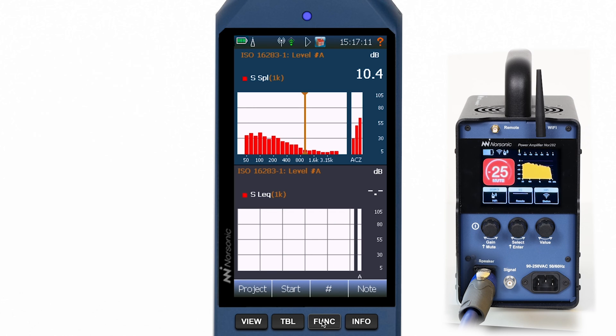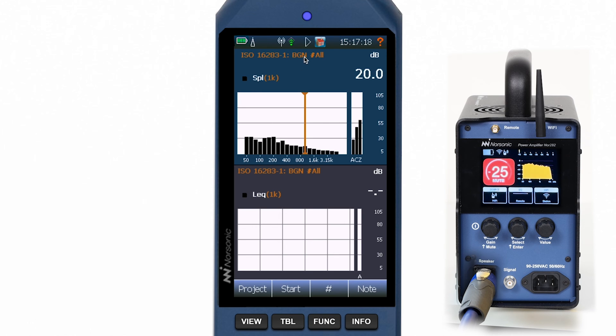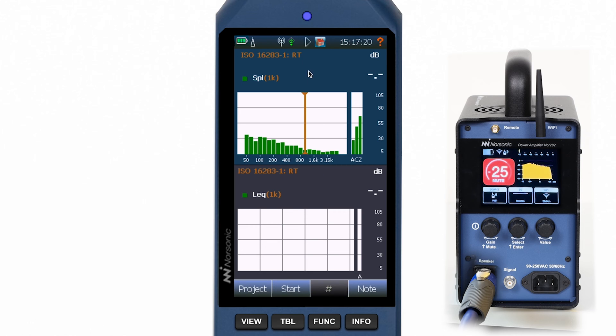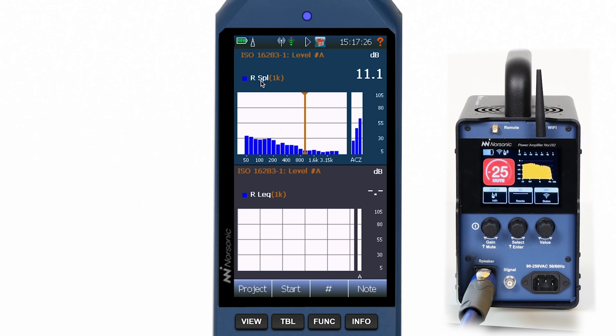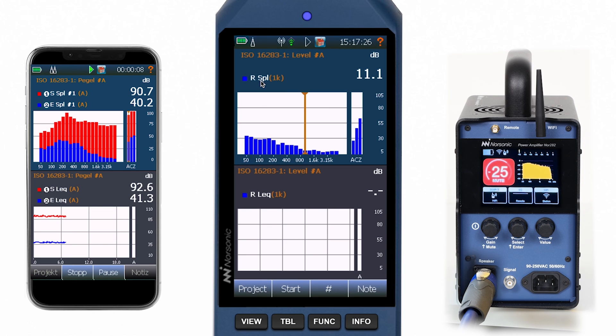We can now simply use the function key to toggle through the type of measurement we want to make. Sending room level is shown in red, background noise level in black, reverberation time in green, and receiving room level in blue. For dual channel measurements, sending and receiving room levels would be shown within one view.